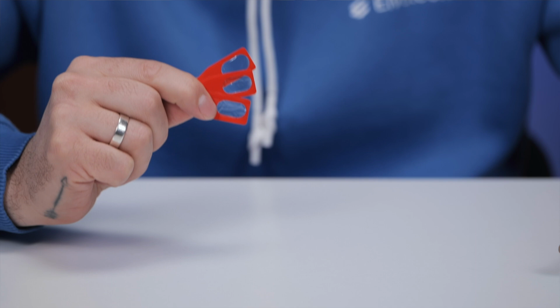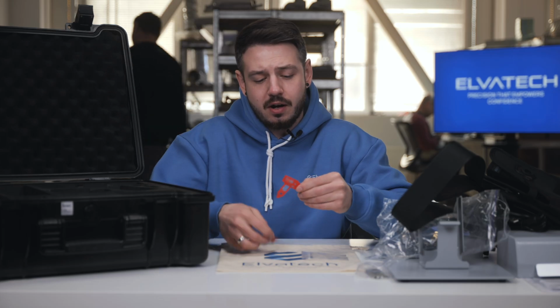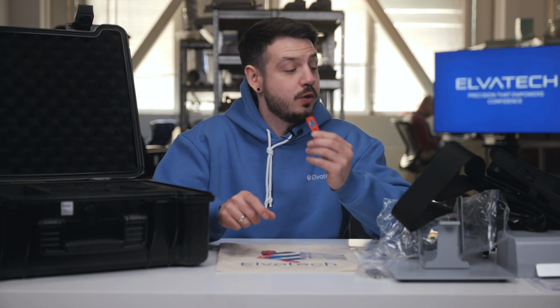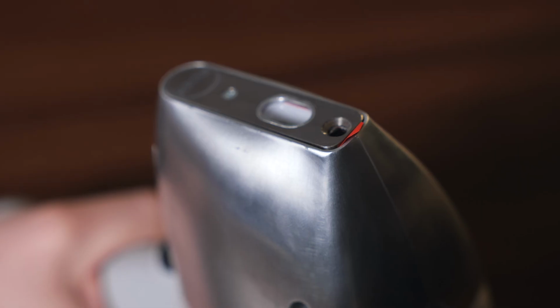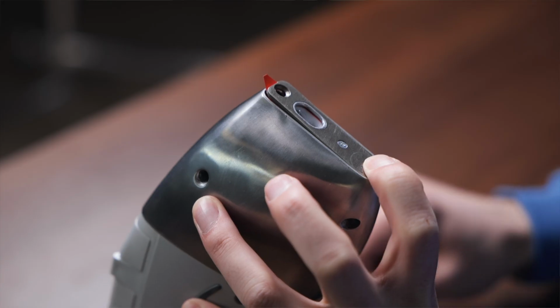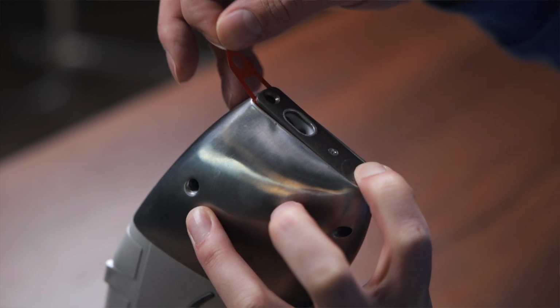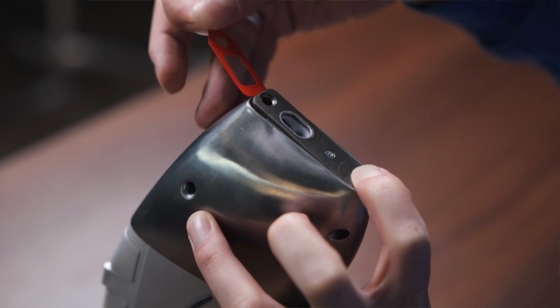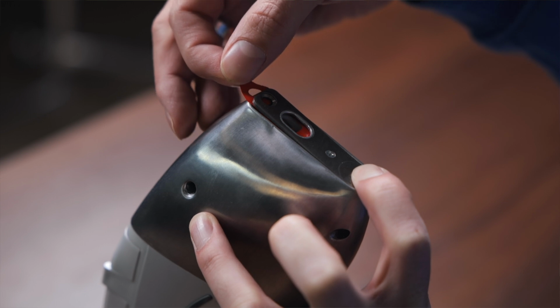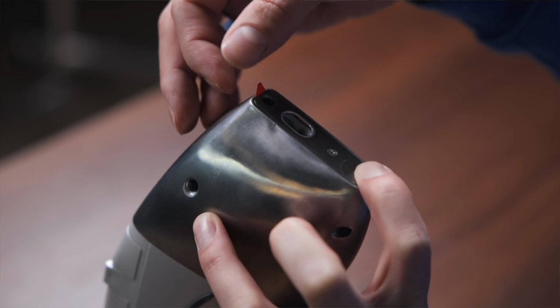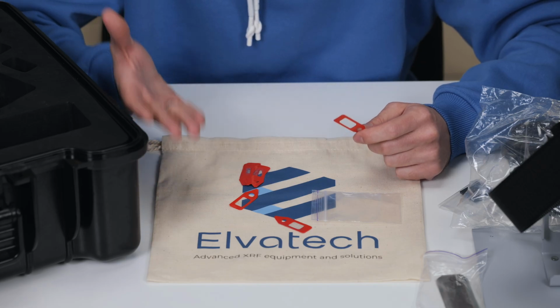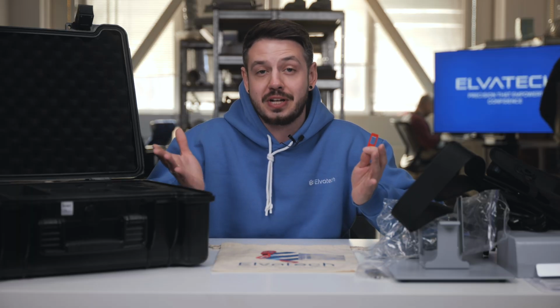And here come our protective windows for the device, which you put on the nose of the device. They help you keep your detector and your tube safe, and also help to prevent any kind of dust or other contamination that your device may pick up. So basically, you will need to change them regularly, like once a month or once every 2 weeks. It all depends on the surface that you work with and your production.